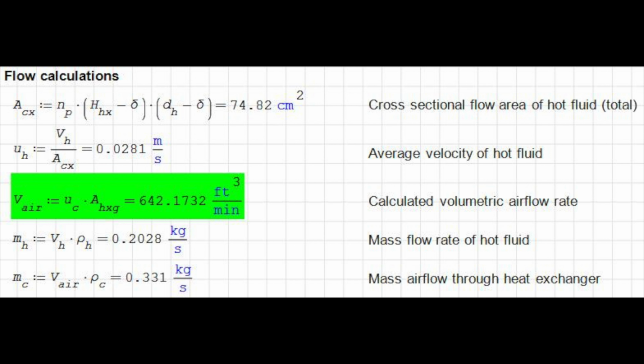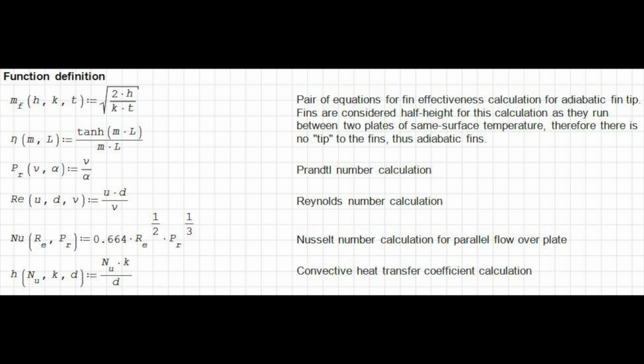Next, we move to the mass flow rate of the hot fluid. This is the crucial one, right? These 2 right here, those are derived from the previous line items using the density. All right, then we move down to definitions of functions. So here we have M and eta, which are calculations that go together to find the functions, the effectiveness of the fins, because there are diminishing returns on lengths of fins. So we'll come back to this, but the fins between the 2 plates will be treated as half length with an adiabatic tip, which means there is no heat transfer from the tip of the fins, but that goes back to the fact that we're treating them as half length because they are between 2 plates.